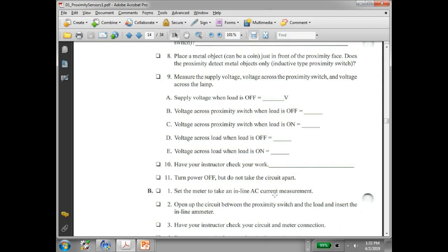Then this is where we got to be careful, because here we're going to start measuring more current. Open the circuit between the proximity switch and the load and insert your inline amp meter. So this is where you need to have these clips, right? You understand that? If you got clips with your meter, they usually come with that. Most people lose those. I have some alligator clip jumpers you can use.